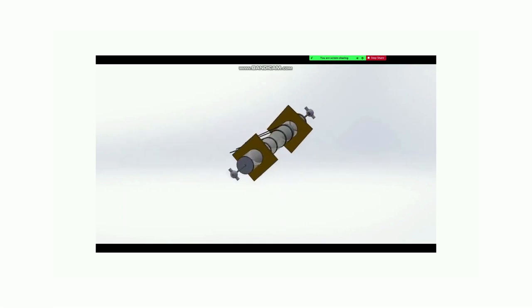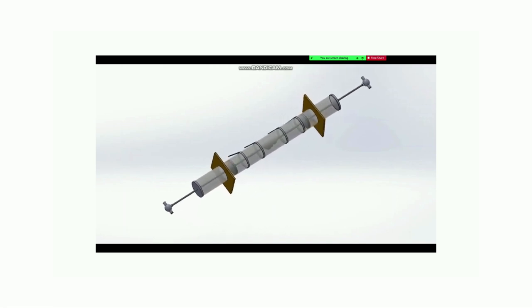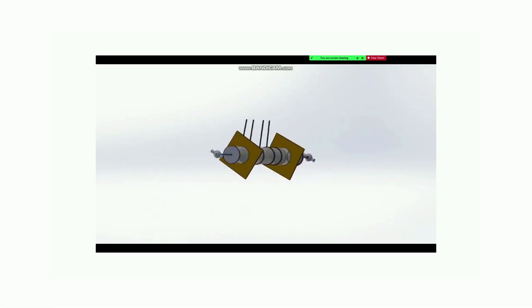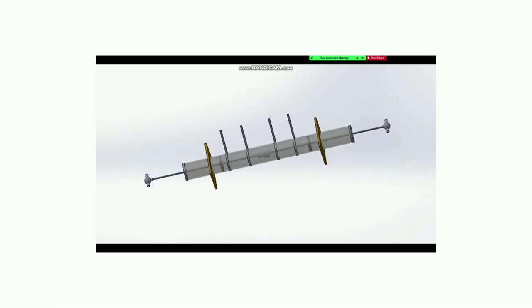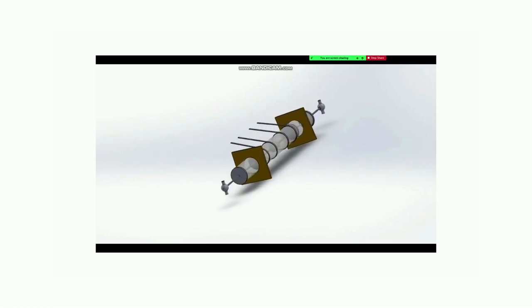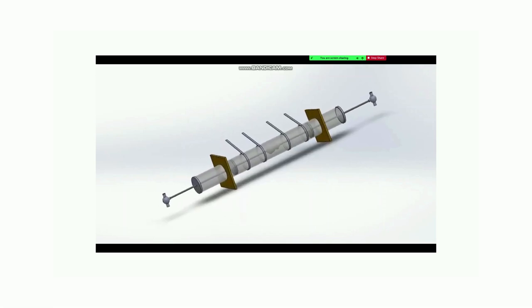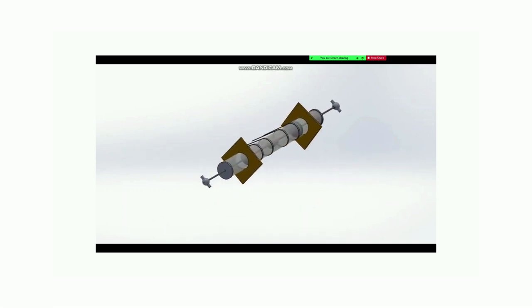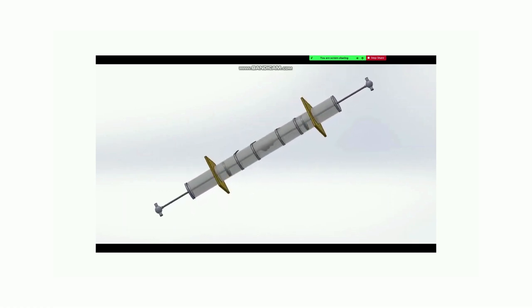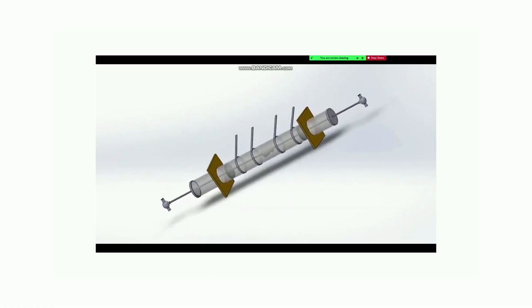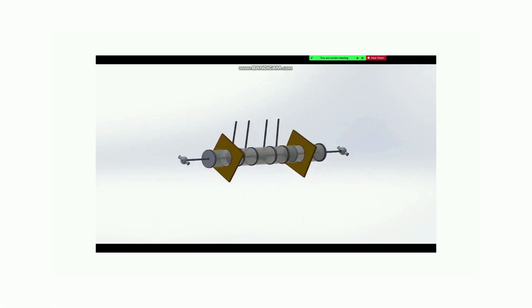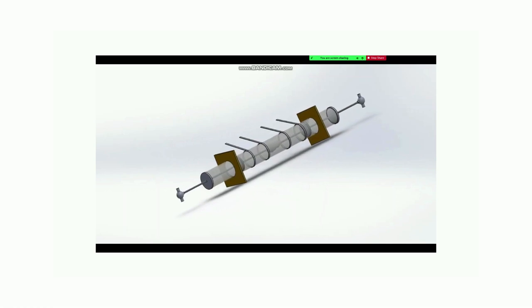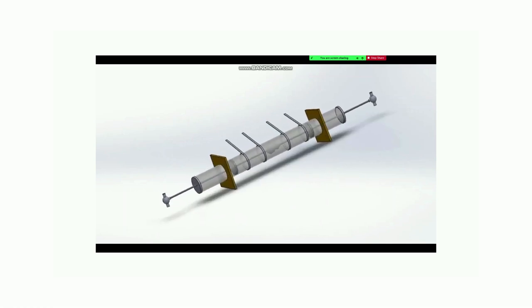This is the model we are expecting to use for the calibration process. The model is expected to accurately reproduce the changes in volume and ionic content of a limb segment in response to arterial blood flow. A model with a 33 cm long plastic cylinder, 9 cm inner diameter, closed at both ends and fitted with four 6 mm wide movable stainless steel band electrodes surrounding the inner diameter. A movable rigid plastic tube 5 mm outer diameter is expected to be installed in O-shaped rings centered at each end of the cylinder. These tubes are expected to be adjusted so that the ends are positioned directly beneath the inner band electrodes. Dialysis tubing is expected to be fastened between the ends of these tubes to provide a flexible, semi-permeable artificial artery.